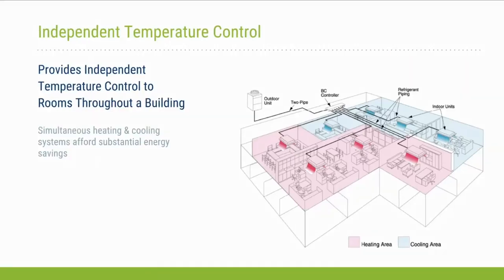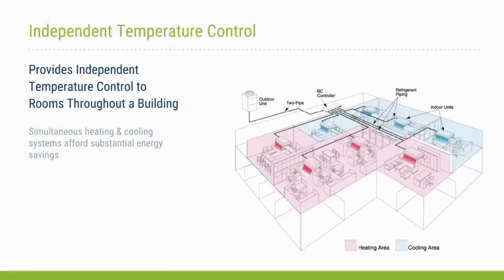The third type of VRF system is the most efficient type, and it's the heat recovery system. The system includes controls that allow simultaneous heating and cooling. Simultaneous heating and cooling systems afford substantial energy savings. And this picture illustrates how the system is able to remove heat from the blue spaces that need cooling and provide it to the pink spaces that require heating. When the heat is transferred this way, the compressor operates less, saving lots of energy.